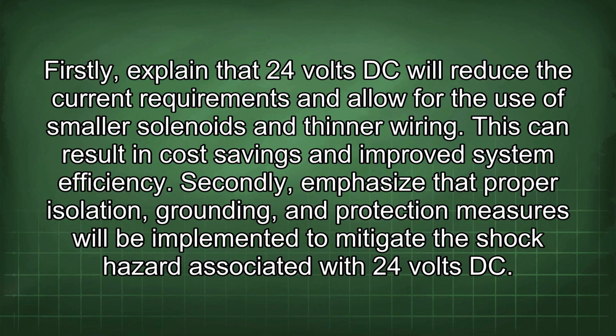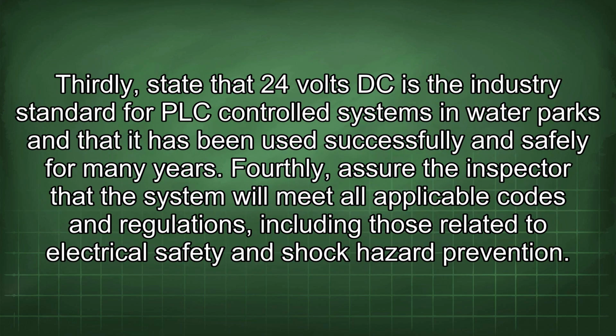Secondly, emphasize that proper isolation, grounding, and protection measures will be implemented to mitigate the shock hazard associated with 24 volts DC. Thirdly, state that 24 volts DC is the industry standard for PLC-controlled systems in water parks and that it has been used successfully and safely for many years.